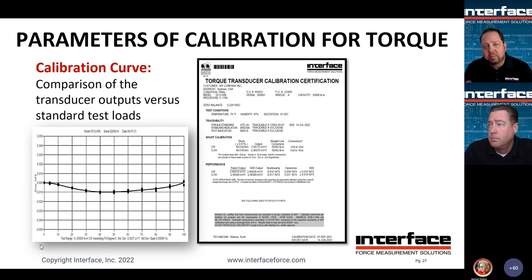But you have basically rated output in both directions for a torque sensor, and on the left there is the sample output curve. Ideally, a transducer is perfectly linear. Of course, we know they can't be. In this case, this stayed within 0.01%, so not too bad. And there's the actual cal data, both directions, or I should say at least, excuse me, it's ascending, it looks like. And so you've got some slight deviation there. This is a multiple run.